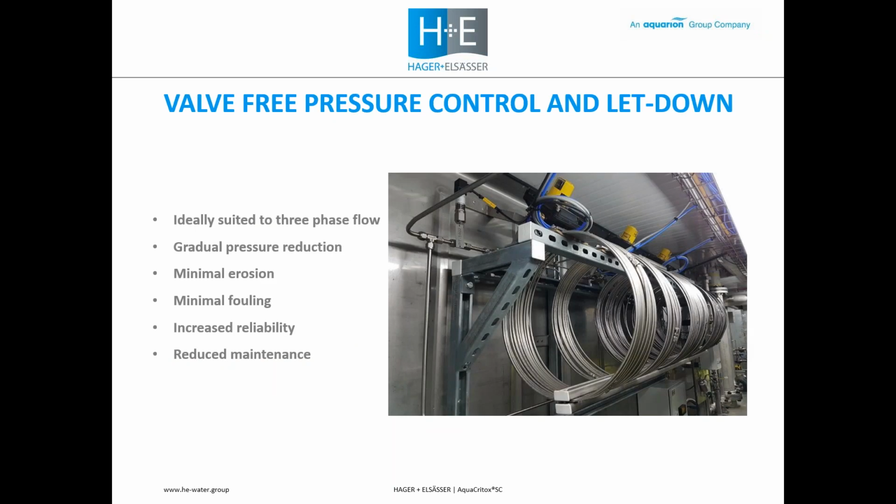The valve-free pressure control and letdown system. Now, you can appreciate that operating at 165 bar and with elevated temperatures is going to cause havoc with a conventional pressure letdown system. So you're dropping large pressures across a small control valve. You have potentially suspended solids. It's an extremely aggressive process. So to overcome this, SCFI have come up with a novel, patented system to let the pressure down gradually.